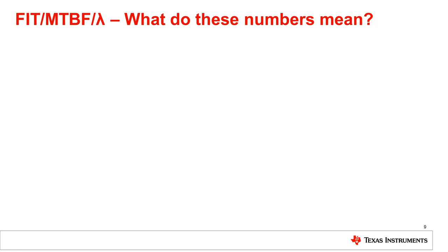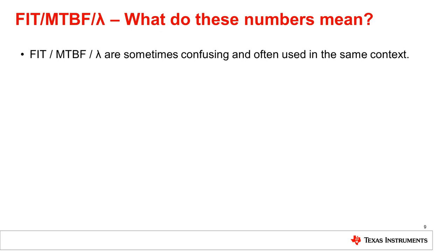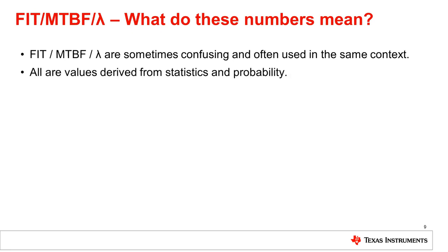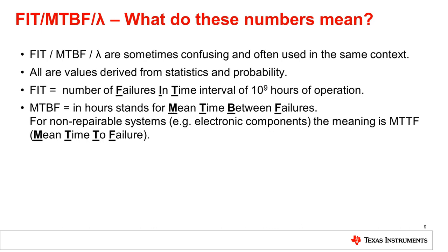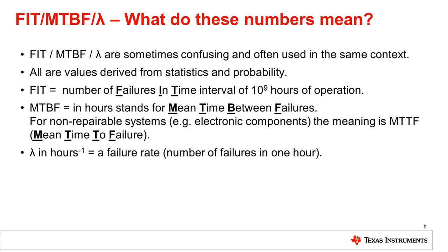FIT, MTBF, and Lambda are sometimes confusing and often used in the same context, but all are values derived from statistics and probability. FIT is the number of failures in a time interval of 10 to the 9th hours of operation — that is, the FIT number is the number of failures in 1 billion hours of operation. MTBF is also given in hours and stands for mean time between failures; for non-repairable systems such as electronic components, the meaning is MTTF, which is mean time to failure. Finally, Lambda is given in hours to the minus first — it is a failure rate, which is the number of failures in one hour.